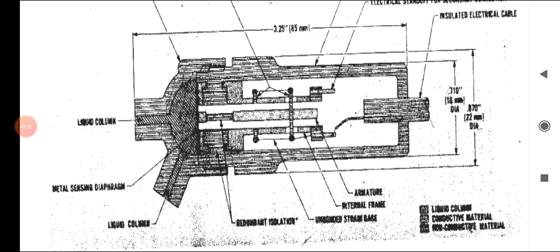So this is a liquid column transducer. Here three modes of isolation are provided. One is external isolation, which provides protection from extraneous voltages. Second is redundant isolation, which isolates bridge elements. The third is additional isolation, isolation of the frame from the case and diaphragm. In another transducer, strain elements are diffused on a tiny silicon beam.